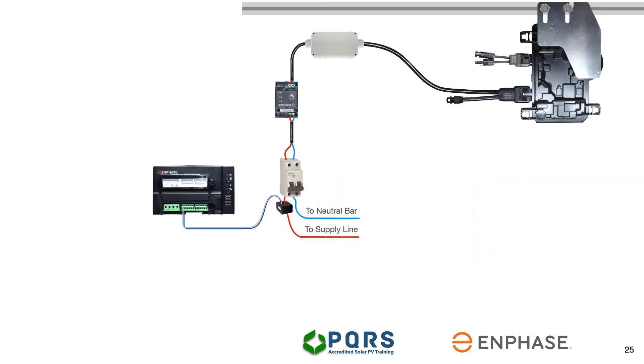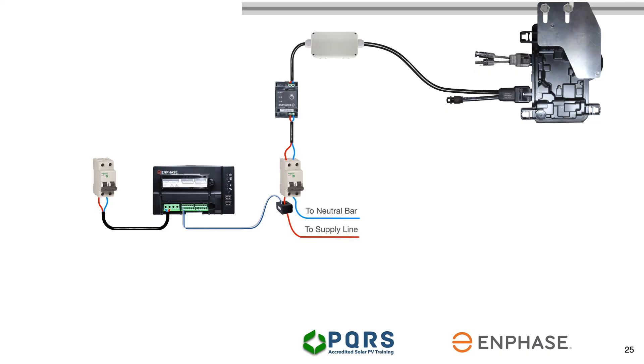The Envoy also needs to be kept alive and we will need a power point that can be powered from a circuit breaker. The Envoy is supplied with 200-amp CTs in the box. The one CT will be used for production data and the other for consumption data.